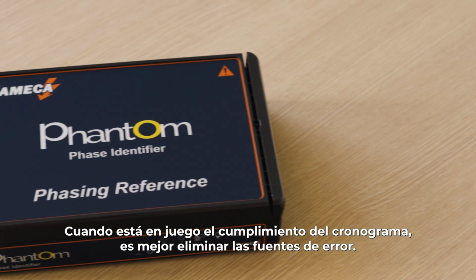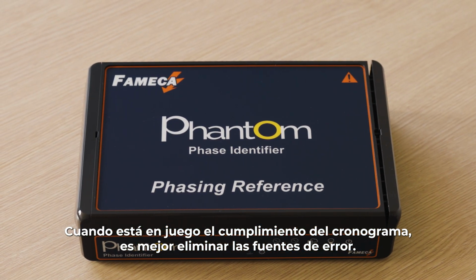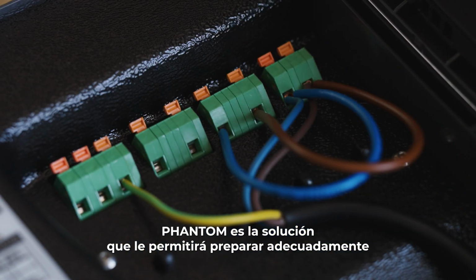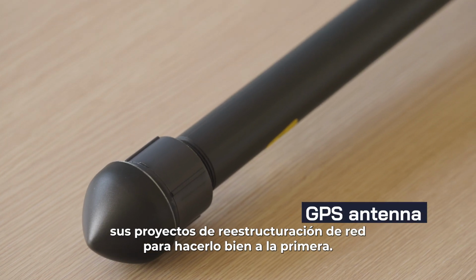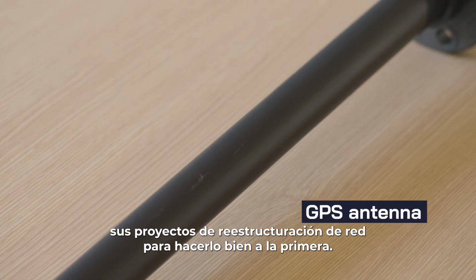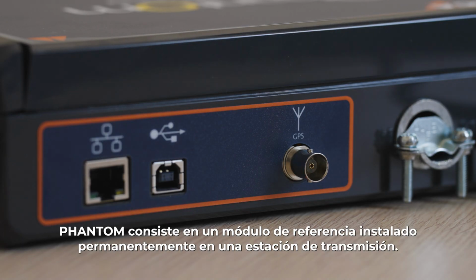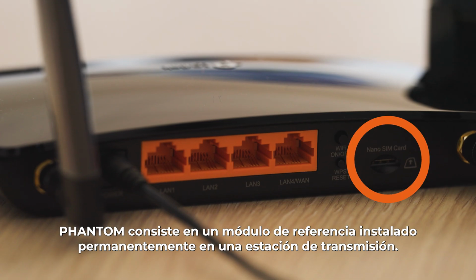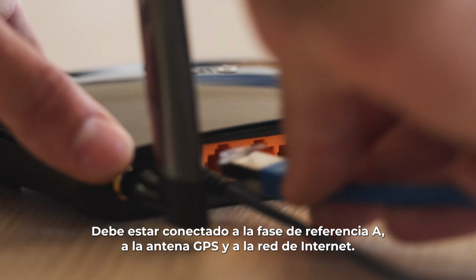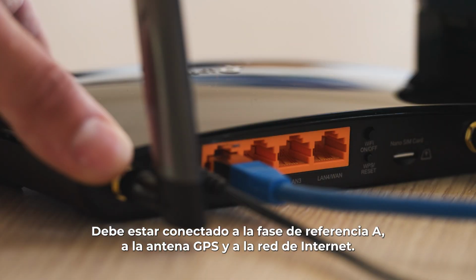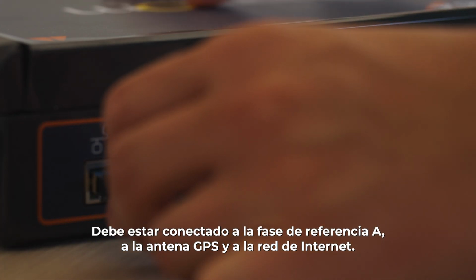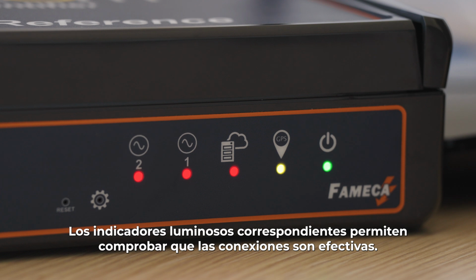When schedule compliance is at stake, it is better to eliminate sources of error. Phantom is the solution that will allow you to properly prepare your network restructuring projects to do it right the first time. Phantom consists of a reference module permanently installed in a transmission substation. It must be connected to the reference phase A, to the GPS antenna, and to the Internet. Corresponding green light indicators show when the connections are effective.